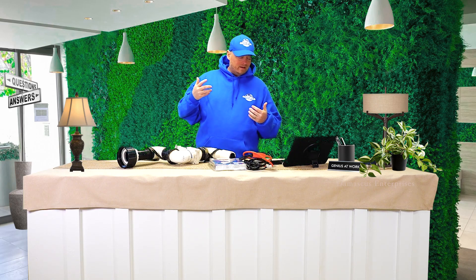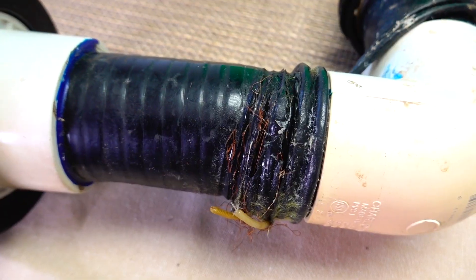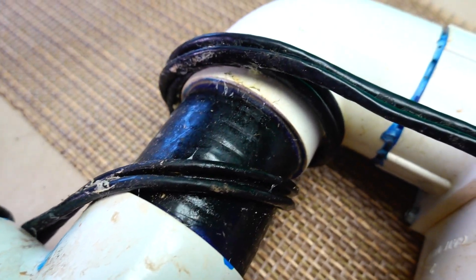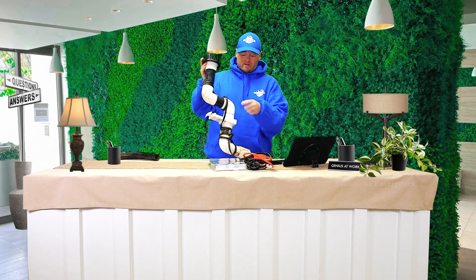Is it safe to use on PVC pipe? The answer to that question is yes. However, if it's not installed properly, you can have an issue such as this here. This was installed improperly by a customer — it was wrapped too close to each other, got too hot, and actually melted the pipe, causing a leak.